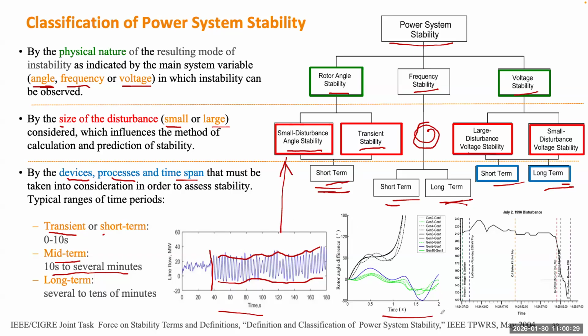The second: you have many generators in the system, but after a disturbance, one group of generators flies away from the rest of the system. This is a typical example of transient instability. And the third one is the voltage at one substation around 230 kV. After a number of events, the voltage can go up and down, but it always stays around the nominal voltage, then suddenly drops to a very low value. This phenomenon is called voltage collapse, a typical example of voltage stability. If you want to figure out whether it is a large or small disturbance, at the beginning we may have a phenomenon studied as a large disturbance, and at some stage more like a small disturbance. So it may be both.